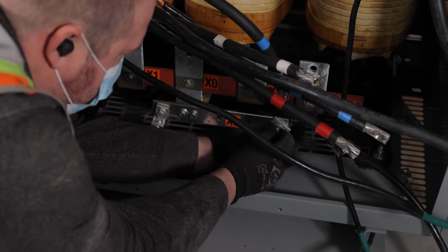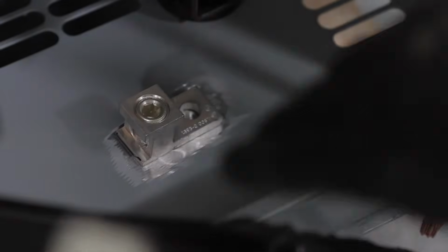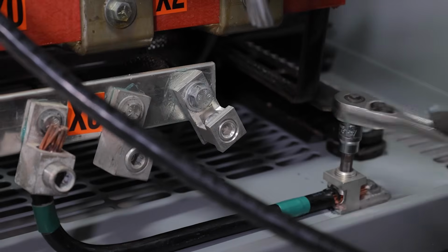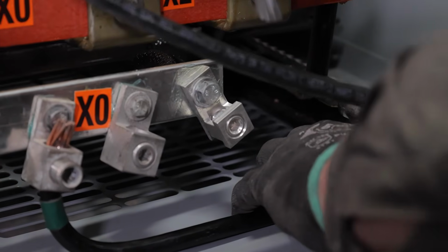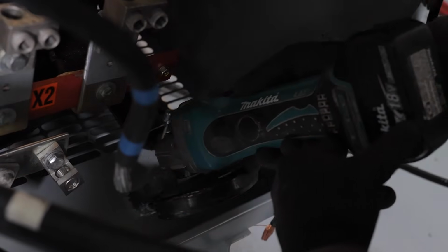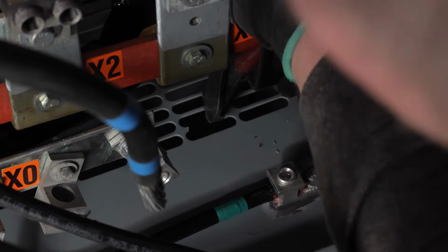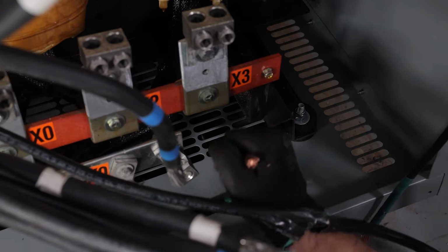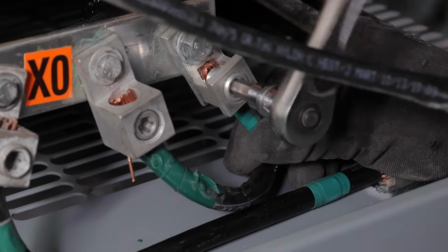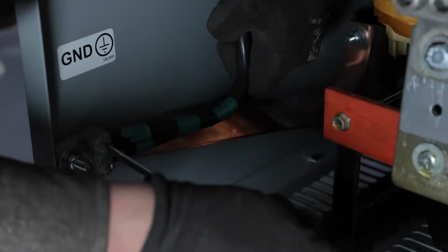In this example, the neutral is bonded within the transformer case, so a ground lug is added and connected to the neutral. The paint on the bottom of the case is removed before the lug is added for a solid connection. A hole is made in the bottom vent to make room for the grounding electrode wires, which are connected to the neutral bus. All other equipment grounds are landed.